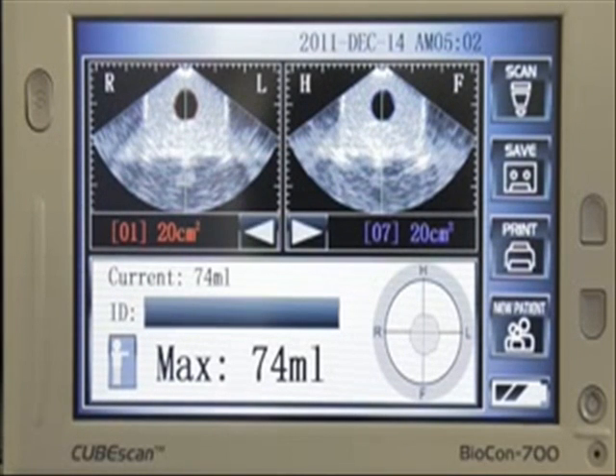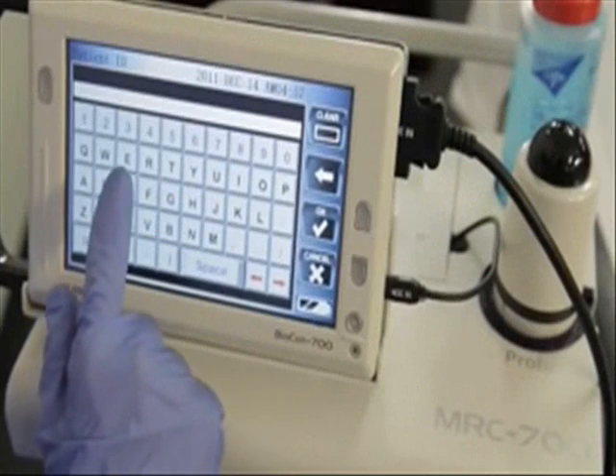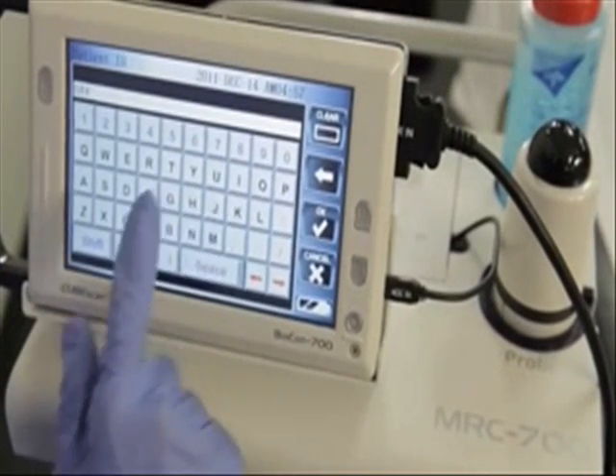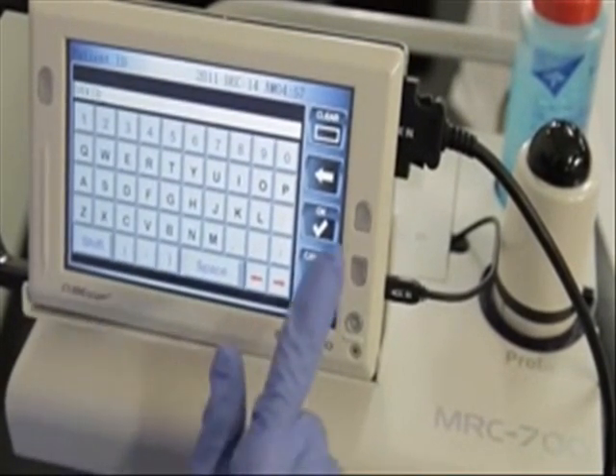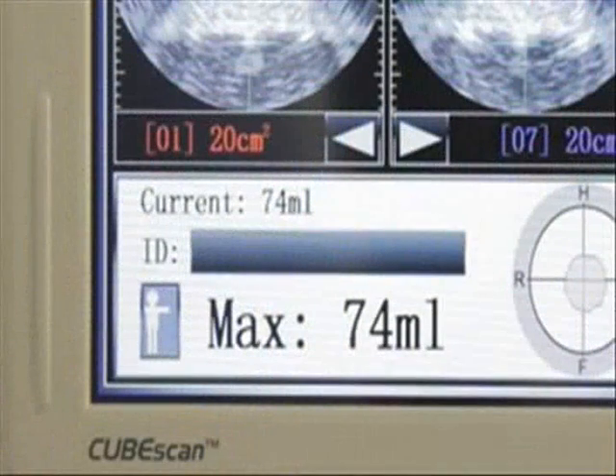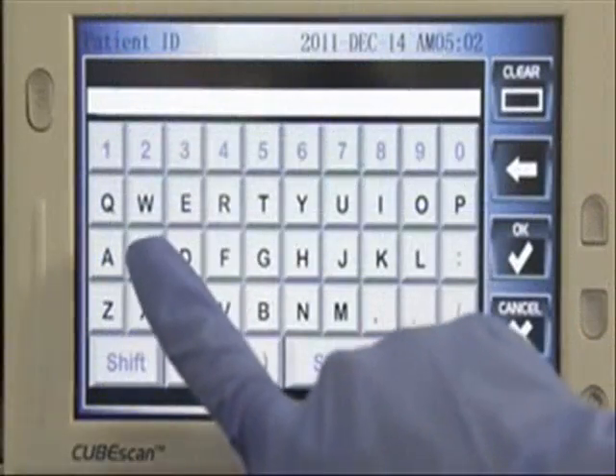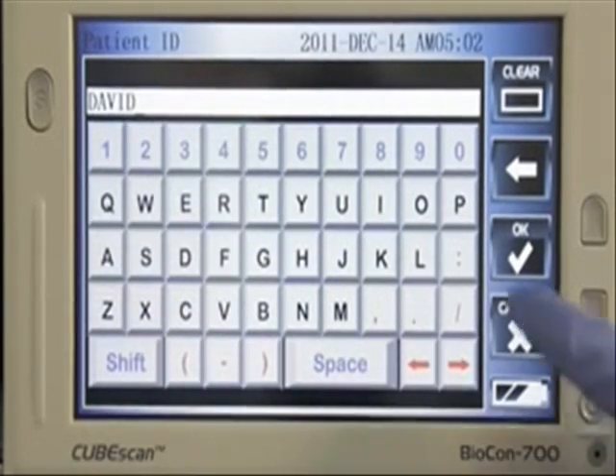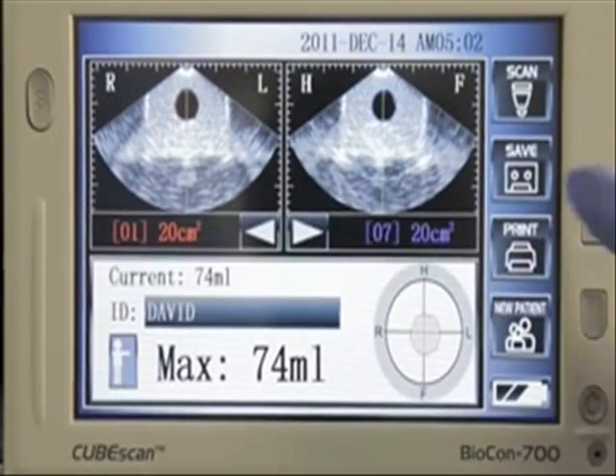If your facility chooses to record the patient identification information along with the readings, you can enter that information using the touchscreen, and it will be saved on the unit along with the measurements. To enter the patient identification information, simply click the ID field at the bottom of the screen. Once you have entered the patient information, press OK. You can store up to 700 patient scans.